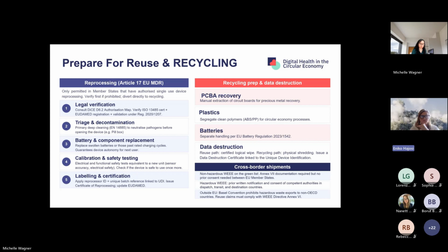The first most important thing to remember when we talk about reprocessing of single-use devices in Europe is that this topic is highly regulated. According to Article 17 of the Medical Device Regulation, it is only allowed in those member states that have specifically authorized this. So the first question is always whether you're allowed or permitted to do this at all where you're operating. If the answer is yes, then we can move through a number of steps. First we need to verify the legal and quality requirements that you see on the slide, like relevant certifications and registrations.